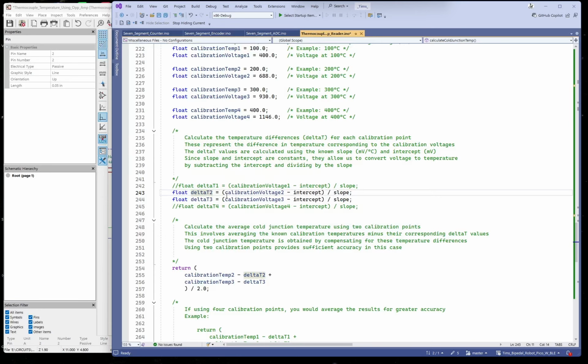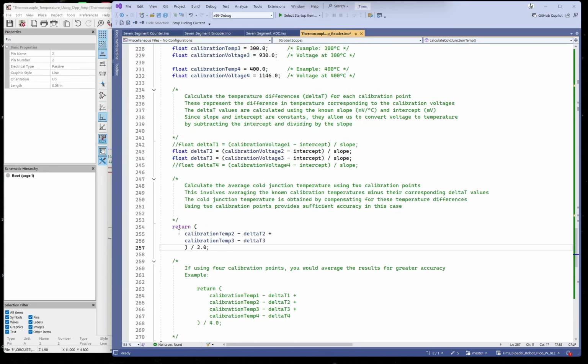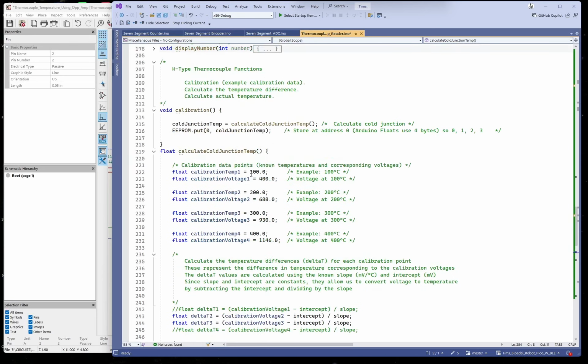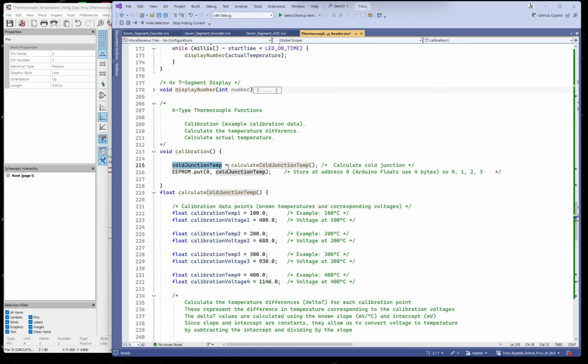Then once we've got the 2 delta T's, we find the average. So basically we just add these 2 together. We take the delta T from the temperature, and then we add the 2 together, divide by 2, and we get the actual returned value. This returns this value function to here, and that gives us our cold junction temperature, which we've found out now. Now that we know that, we can then save that into the EEPROM, and that's what we do here. So once that value there has been calculated and saved into the EEPROM, we can work out, we can convert the millivolts into degrees C.